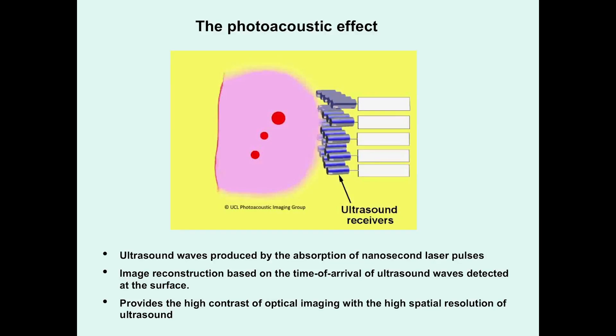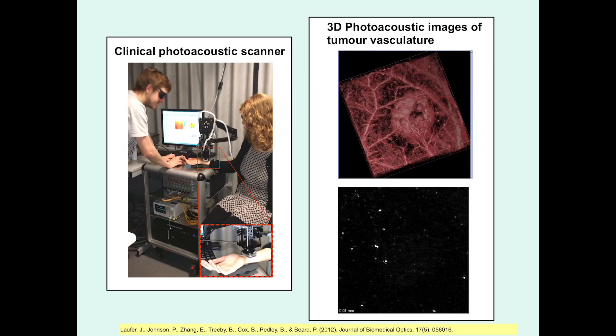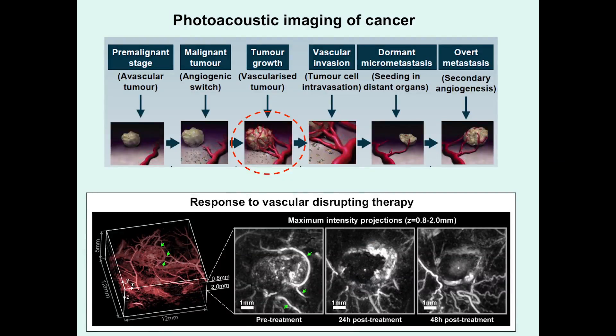And this involves some interesting physics. It involves delivering short pulses of laser light to tissue using light in the near-infrared part of the spectrum where it penetrates deeply. The light gets absorbed and produces broadband ultrasound waves, which then propagate to the surface where they're detected by an array of ultrasound receivers. And from those signals, one can form a three-dimensional image of the internal tissue structure and function.